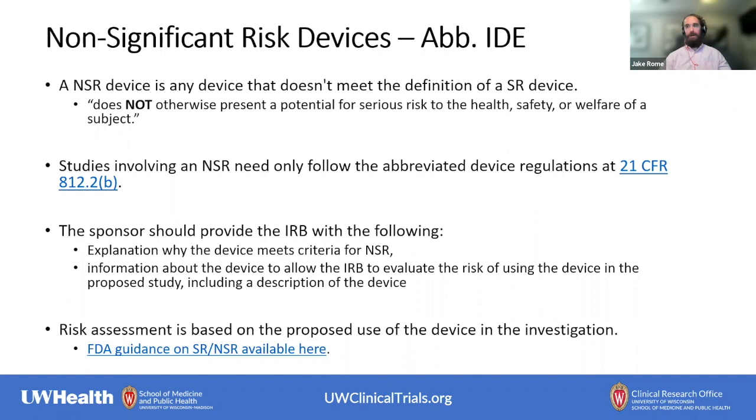But again, as I mentioned before, this assessment is based on the proposed use of the device in the investigation, and not just on the device itself. So again, if you're involving procedures that present significant risk to subjects, even if the device does not, you may be required to submit an IDE anyway. And the FDA has a lot of good guidance on the significant risk versus non-significant risk determination available on their website. We'll make these slides available after the presentation so that you'll have access to all of these links as well.